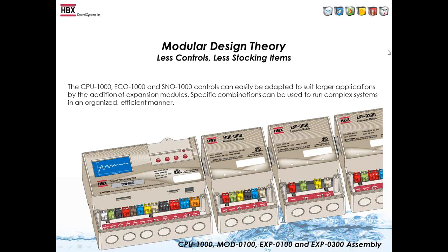The CPU 1000 is a main unit where we can get some smaller installations such as a 2-stage boiler control, some domestic controls, but when you need to get in some larger applications, we decided to have the modules to add on to the main control and expand the capabilities of the CPU and the ECO-1000 to get into some large commercial jobs and even industrial situations. The way we connect the modules is simply by a 32-pin connector that connects easily to the side of the control or another module.